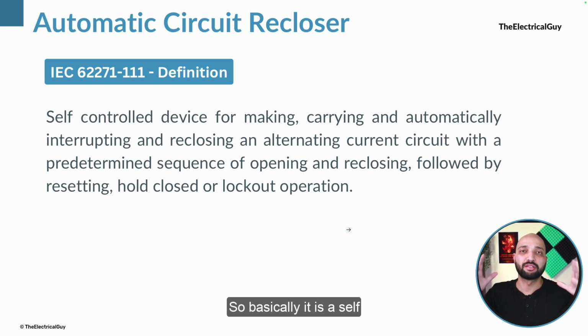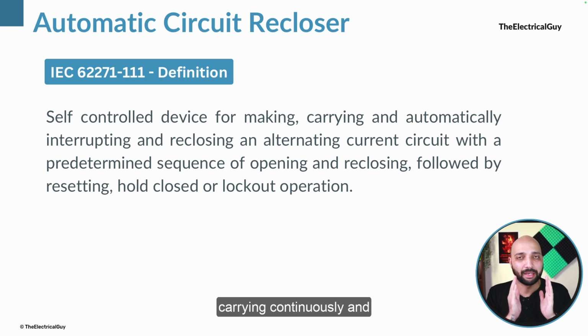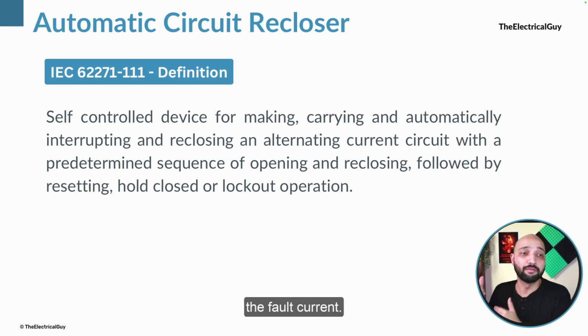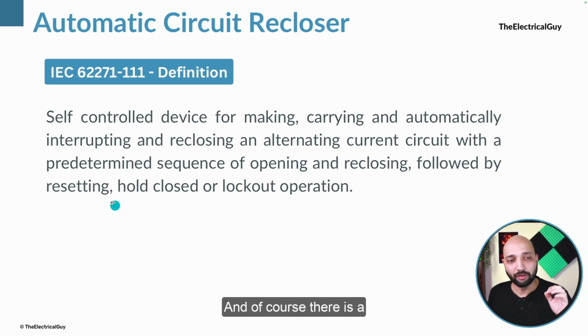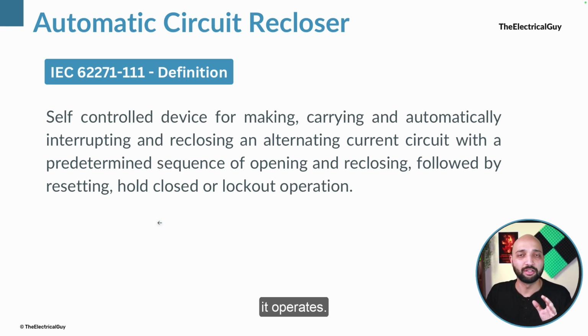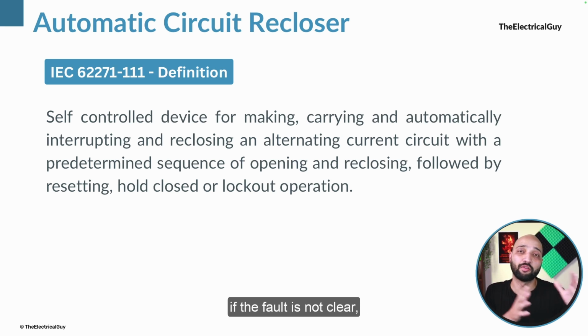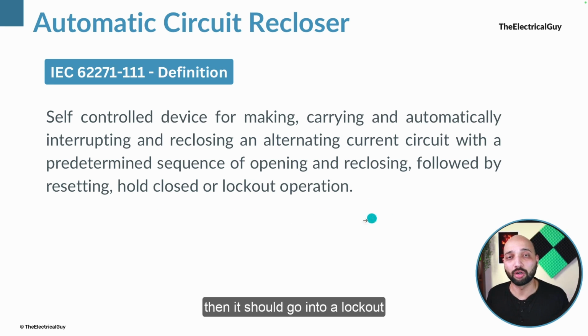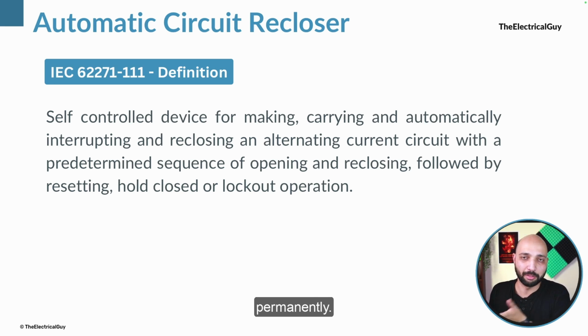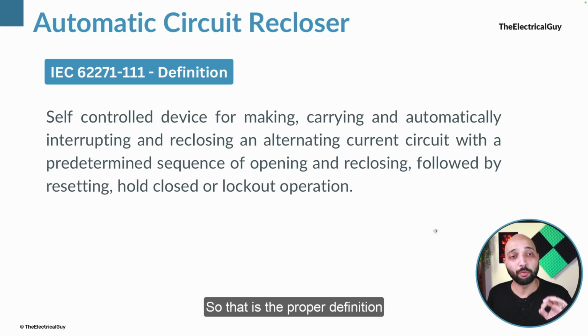So basically it is a self-controlled device which is capable of making, that means closing, carrying continuously and automatically interrupting normal as well as the fault current, right? And of course there is a sequence on which it operates, and after that sequence, if the fault is not clear, then it should go into a lockout situation, or it should be open permanently, and then of course you need to do it manually. You need to manually close that recloser, right? So that is the proper definition given by the IEC standard.